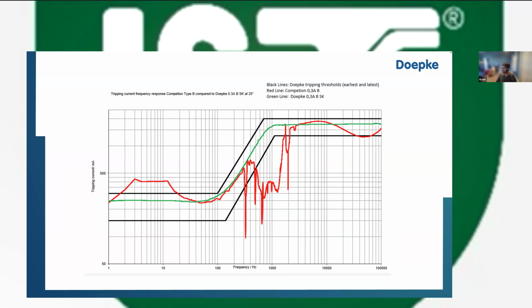Because see, on the x-axis I have frequency, on the y-axis I have current. If the elevator is, say, outputting an 8 kilohertz frequency, or in this particular case, say a 10 kilohertz frequency, this is a 300 milliampere device, for example. This particular red line has this product tripping at a value of, I believe, 60 milliamps. So a 300 milliampere device is tripping at 60 milliamperes here. So that is when you have a nuisance tripping situation where you think a lot of fault current is flowing, but it is not. It's just that the frequency is high. So in the absence of an actual fault, because remember this equipment has some filters inside, what does that look like, I'll get to it. But basically, even 60 milliamps can end up tripping a 300 milliampere device if the wrong type of RCD is used.